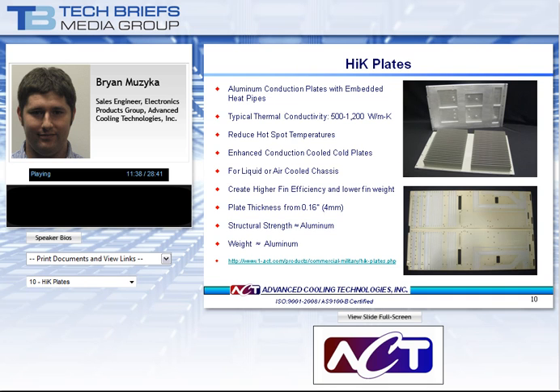After testing the temperature difference along the plate, we went back to the model and inserted a bulk conductivity of the plate and adjusted it until we matched the temperature gradient from testing. Therefore, these thermal conductivity values are a fair estimate and a good way to get a quick check if a HiK plate solution might be good for your system.